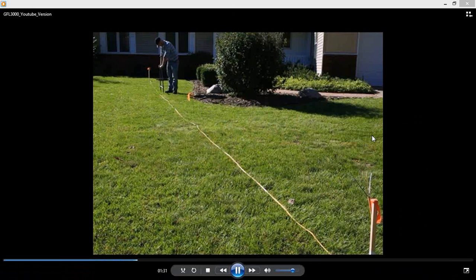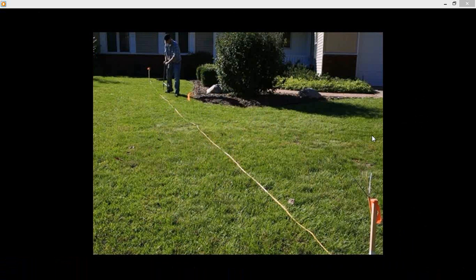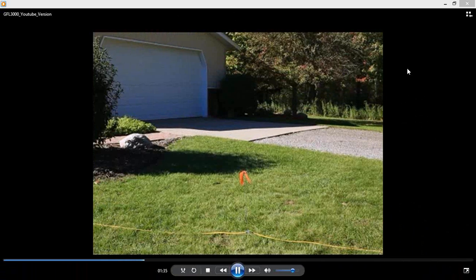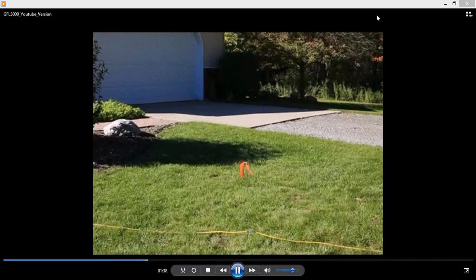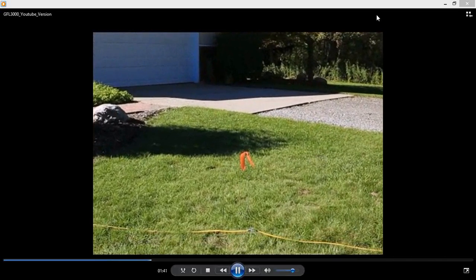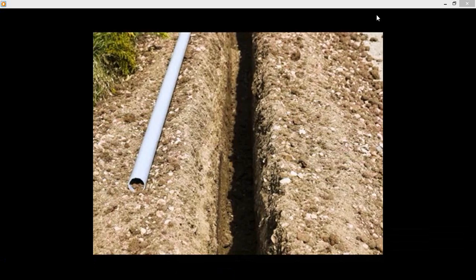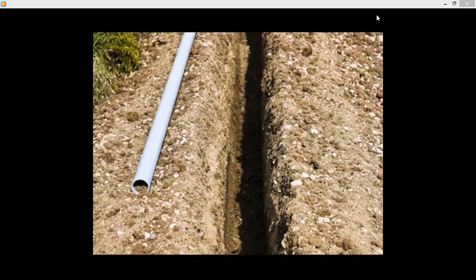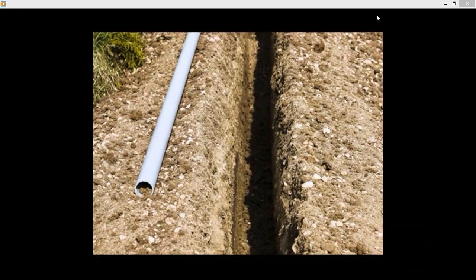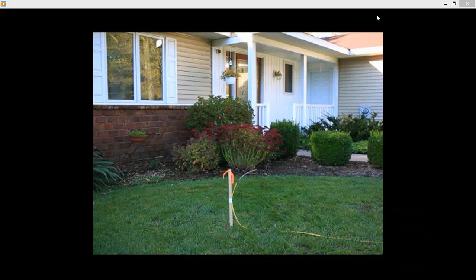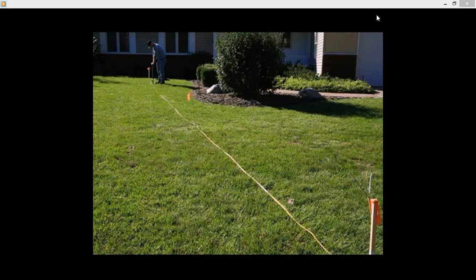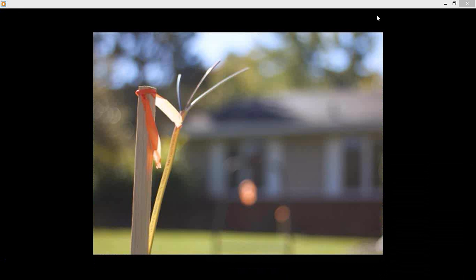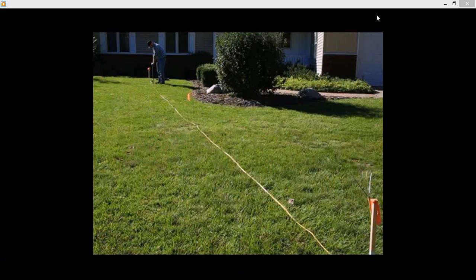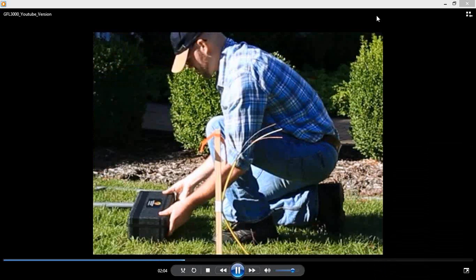To demonstrate that the path of the wire has been previously determined, the wire has been placed above ground. The fault is illustrated with a flag for further clarity. In cases where the wire is contained in conduit, the conduit will interfere with the locator signal and not result in an accurate reading. Isolate the cable to be tested by disconnecting it at both ends. Make sure the cable is disconnected from power, components, or anything else that could transmit an electrical current. This forces the current generated by the transmitter to exit the cable at the fault.